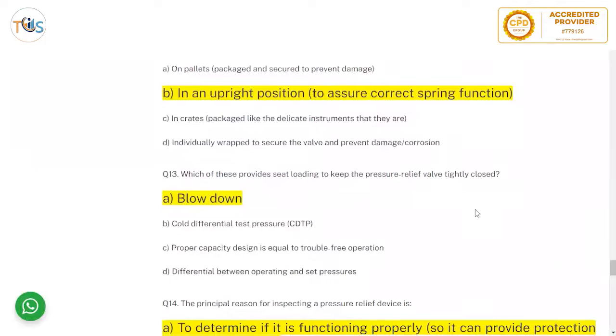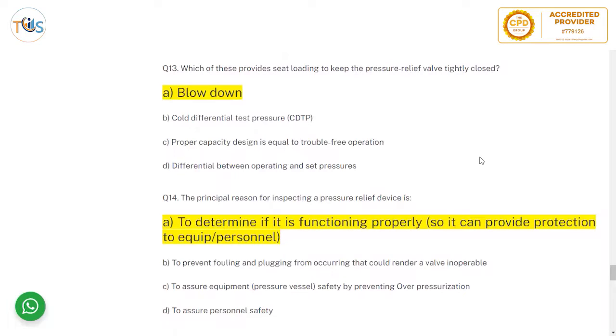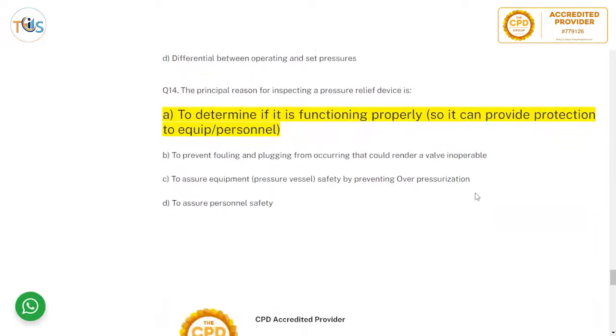Pressure relief valves should be shipped in the upright position, to keep the stem and seats stable. The spring provides seat loading to keep the pressure relief valve tightly closed — closing the valve after blowdown by pressing the disc back against the seat. The principal reason for inspecting a pressure relief valve is to determine if it is functioning properly — not merely to prevent fouling or to assure general equipment safety, as those are secondary considerations.